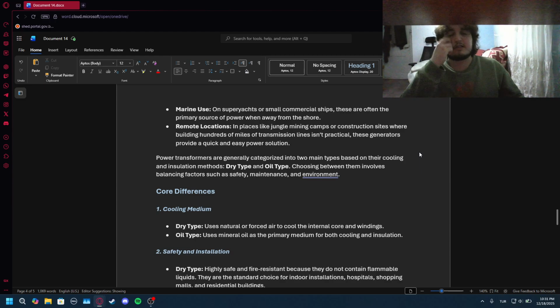Now, let's get to the fun part, in my opinion. Transformers. Power transformers are generally categorized into two main types based on their cooling and insulation methods: dry type and oil type. Choosing between them involves balancing factors such as safety, maintenance, and environment. Core difference: cooling medium. Dry type uses natural or forced air to cool the internal core and windings. Oil type uses mineral oil as the primary medium for both cooling and insulation.